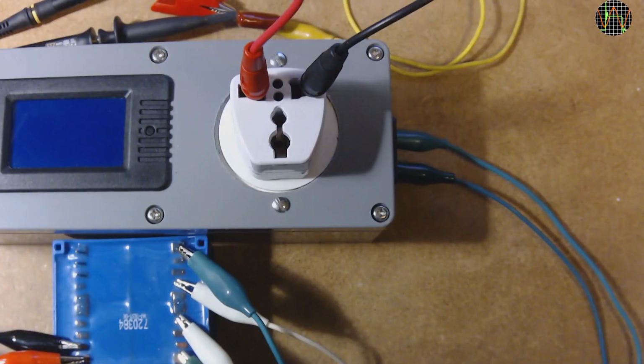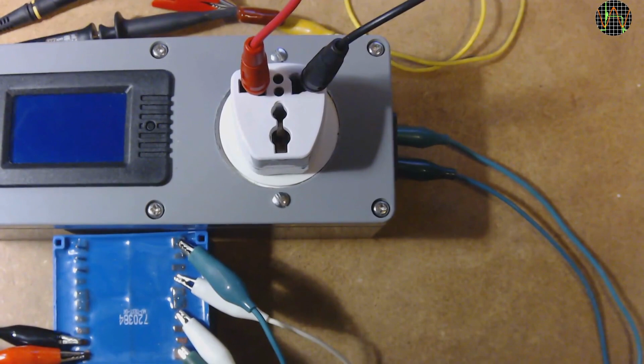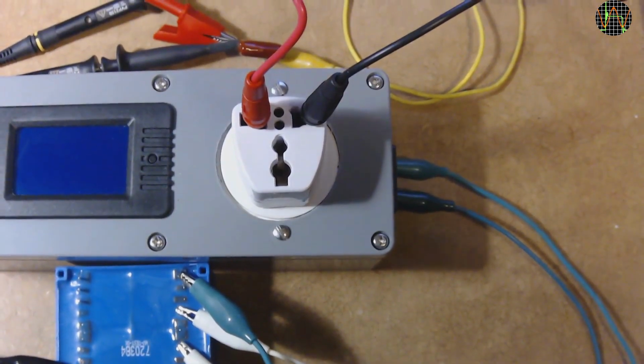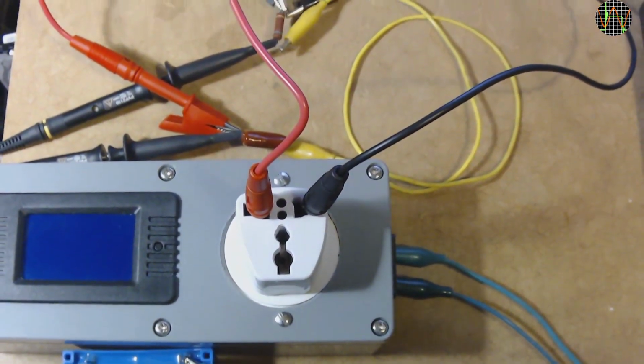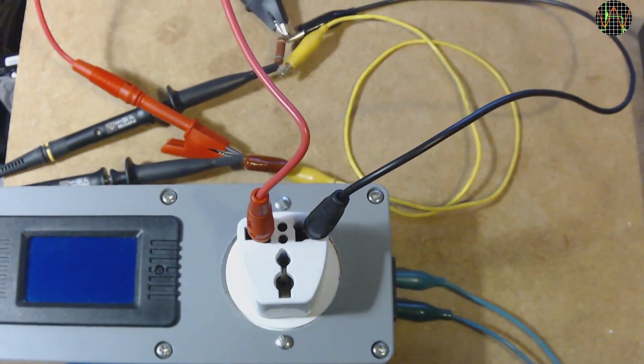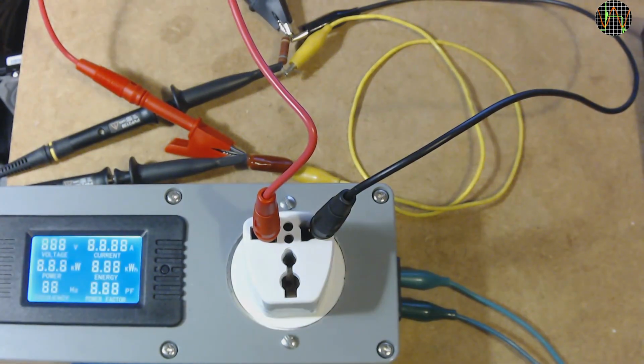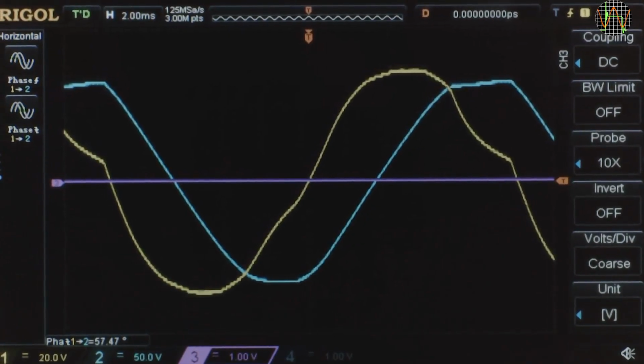You can see the transformer providing the isolated high voltage going into the input socket of the power meter. The capacitor and resistor circuit is connected to the output, and you can see the scope probes and the black lead are used to connect the common scope ground. On turning the power on, the meter shows a current of 30 milliamps, 1.45 watts and a power factor of around 0.51. The yellow trace of channel 1 is the current and the blue trace of channel 2 the voltage.